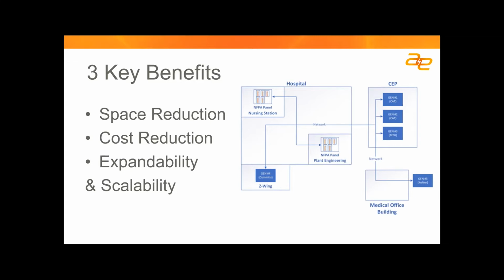One challenge I didn't mention: as an owner, if you have a generator in an area—say a central energy plant—and you expand that plant and add one or two more generators, it's going to raise a flag that results in the existing generators having to be brought up to current standard and compliance. Depending on when those previous generators were installed, that could mean adding alarms, since some older standards didn't require certain types of alarms to be annunciated. So those are some of the challenges that can happen with an evolving standard when you add more generators to an existing facility.